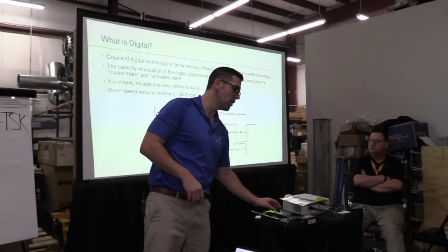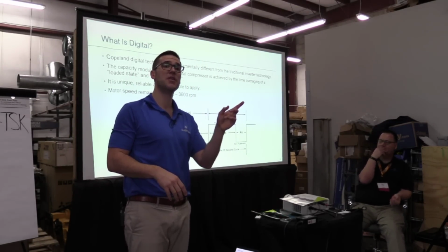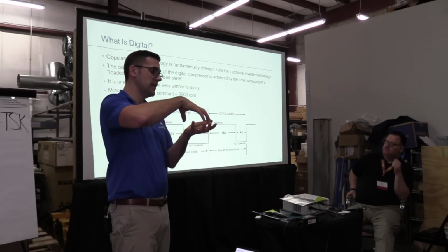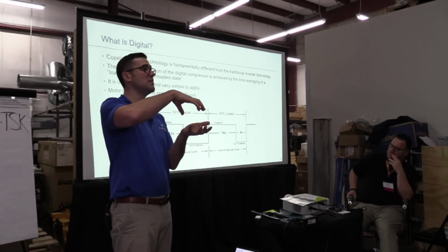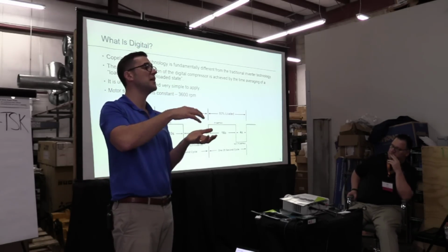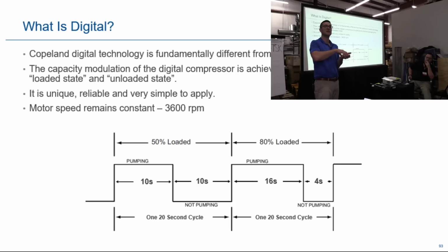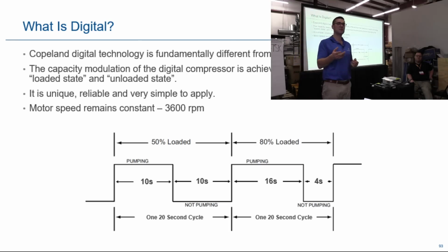So the way the digital works, remember we talked about axial compliance? What it does is separate, and it's all done on time, either 15 seconds or 20 seconds, depending on what type of compressor you're putting in, right? So if it's pumping for 10 seconds and unloaded for 10 seconds on a 20-second cycle, what's your capacity? 50%, right? So a 100,000 BTU compressor that pumps for 10 seconds and unloads for 10 seconds is 50,000 BTUs. And it sounds like it's going to detonate. You swear you got a bad compressor.